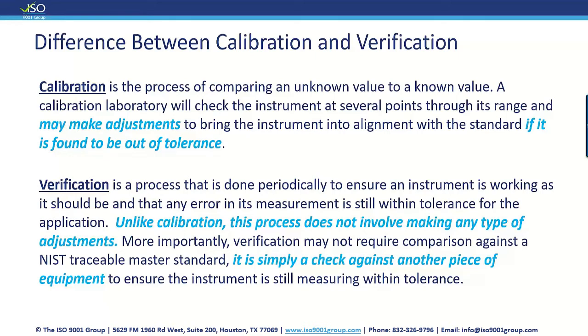Now, if you put that 5-pound weight on your scale at home and it's not reading correctly, but even that scale has a tolerance, a plus or minus within a certain range that is acceptable. If it's outside of that range, then you may look at taking your scale to a calibration or repair facility, or may just replace it, right? It may just be cheaper to get a new one.